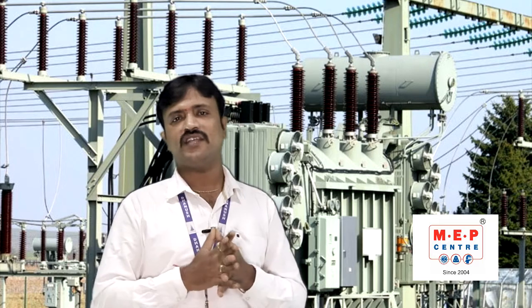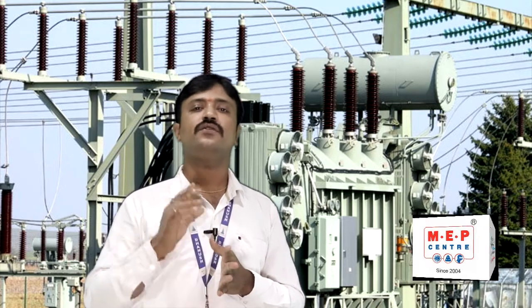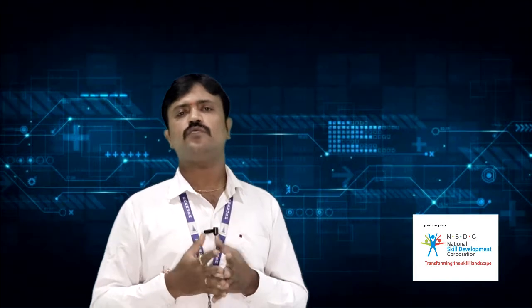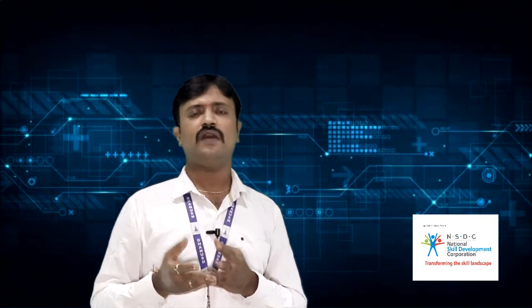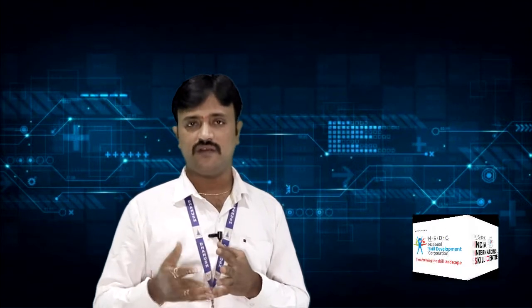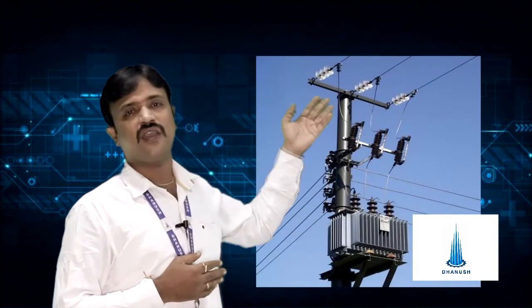Okay, now once you have the transformer size, the most important thing is we need to define the point of supply. Now what is point of supply? We have different level kV lines, different point of supply levels, like 33 kV, 66 kV. So once you have the transformer in kVA, how much kVA is required, then based upon that kVA, we are going to decide the point of supply, whether it's a lower level kV line, a 33 kV line, or a 66 kV line. That is about the point of supply decision.